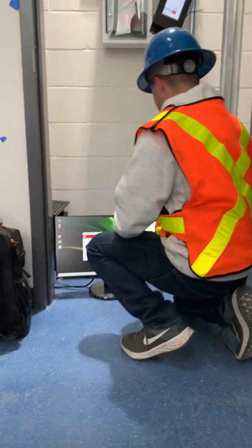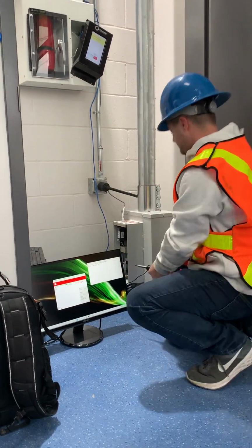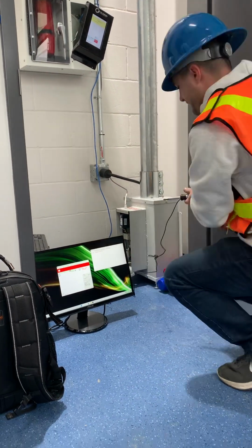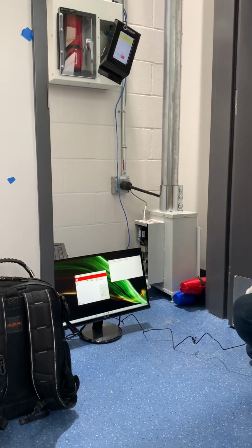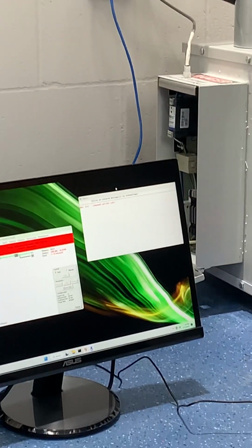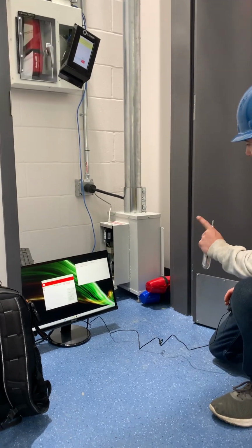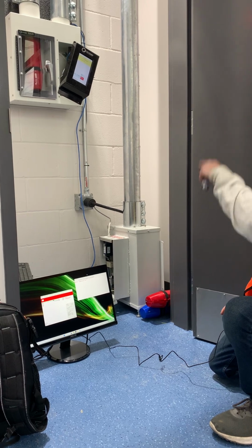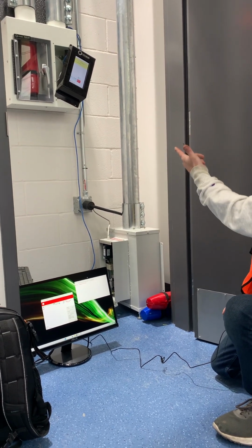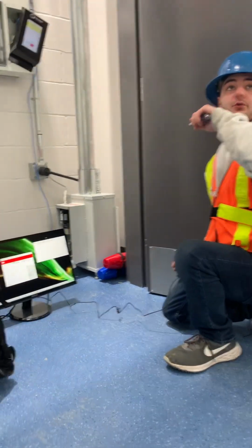So let's say I figured out the problem. So right here it says inbound carrier late. So let's say I go to the hospital and I'll get a lot of these error codes, and what would happen is either, well, I just showed you the optic could be bad and then it threw it into an alarm because it can't tell that it made it here.